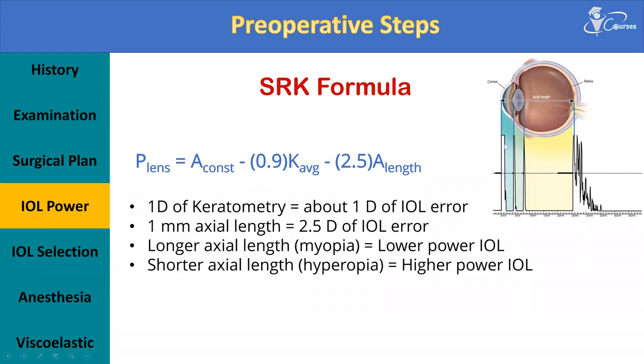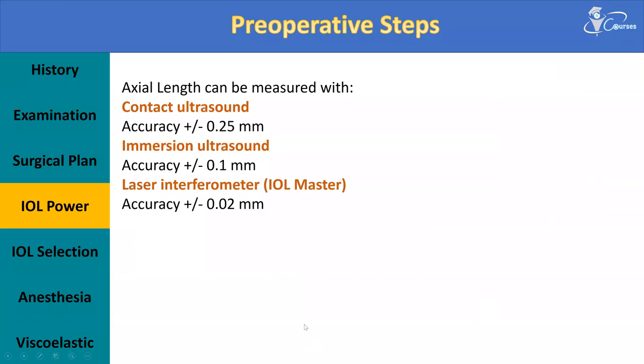If the spikes representing the anterior and posterior corneal surface, the anterior and posterior lens surface, and then the retinal surface are not on the same level, you expect that you are not perpendicular to the surface of the globe, so you should adjust your position again. So poor waveforms also should be checked in the biometry report.